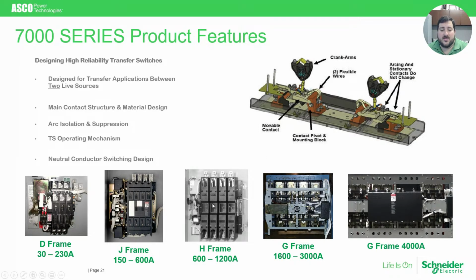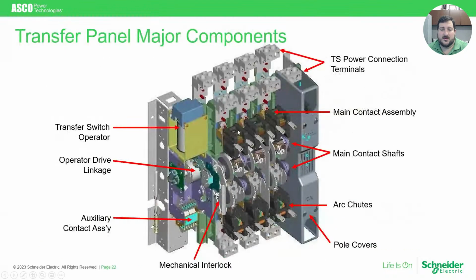The switches really are composed of two key areas, like I mentioned in the video. There is the operator, and then there's the pole assembly, which is where the switching between the sources actually happens to feed the load. Let's take a closer look at one of those pole assemblies and switches. Again, you see the operator on the left-hand side here, followed by several pole assemblies based on the pole configuration of the switch. You can have a single phase piece of equipment with only 2 poles, or you could have 3 poles or 4 poles, depending if it's a 3-phase system. And if you are switching the neutral or require a solid neutral, all those things would contribute based on your needs for the application.